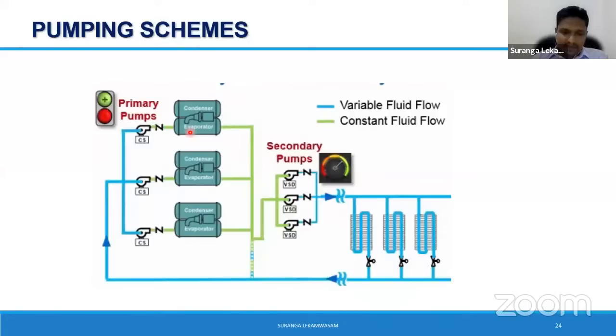When you refer to the chilled water side, which is important, in industry you can find two pumping schemes. One is called the primary and secondary pumping scheme, which you can see here. There you can see two loops, actually, right? This is my chilled water loop, the chiller loop. This is my load side loop.